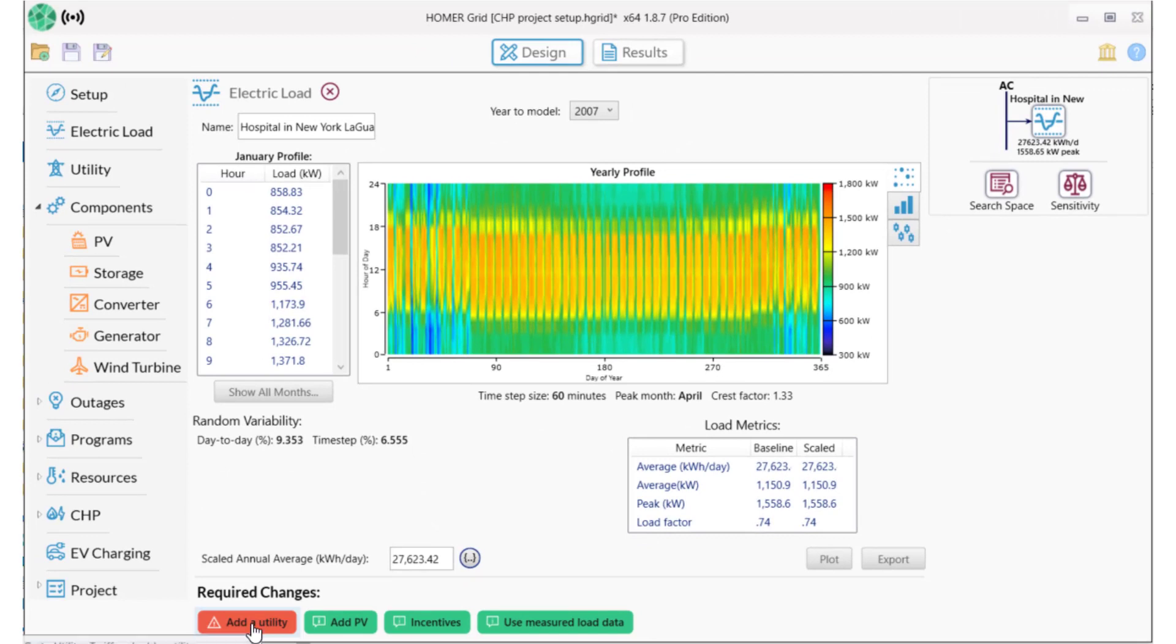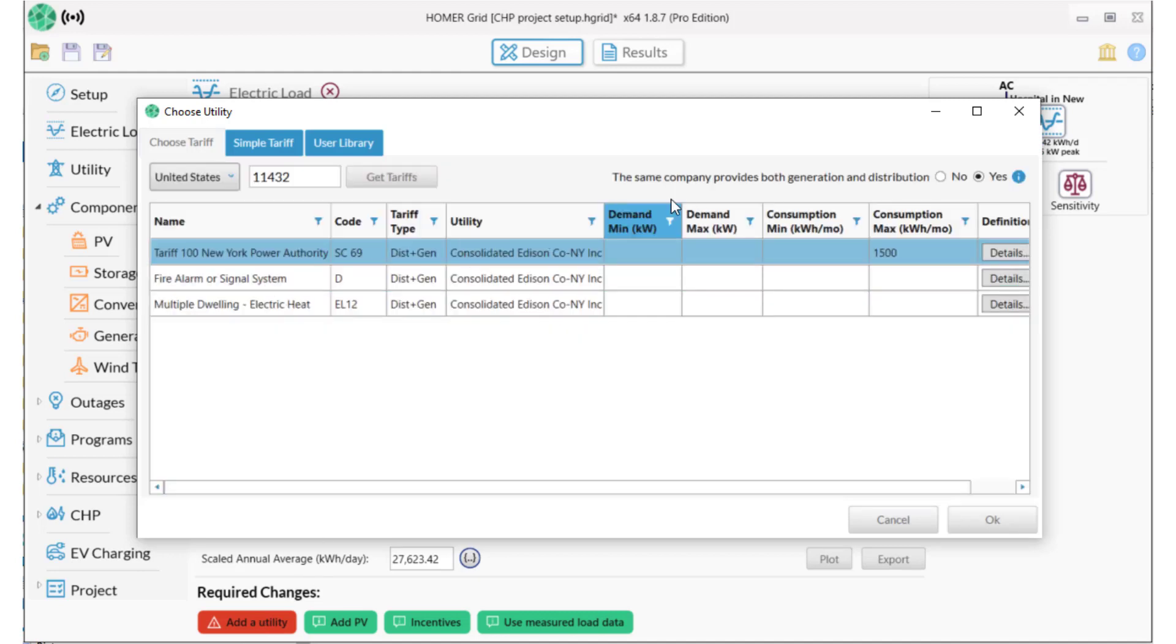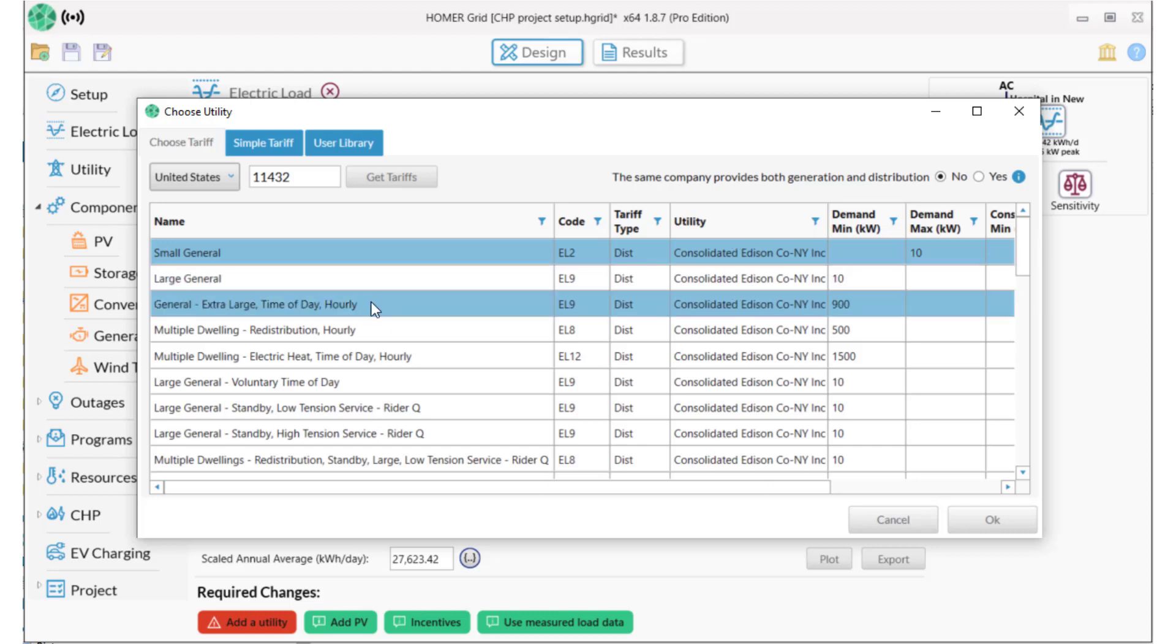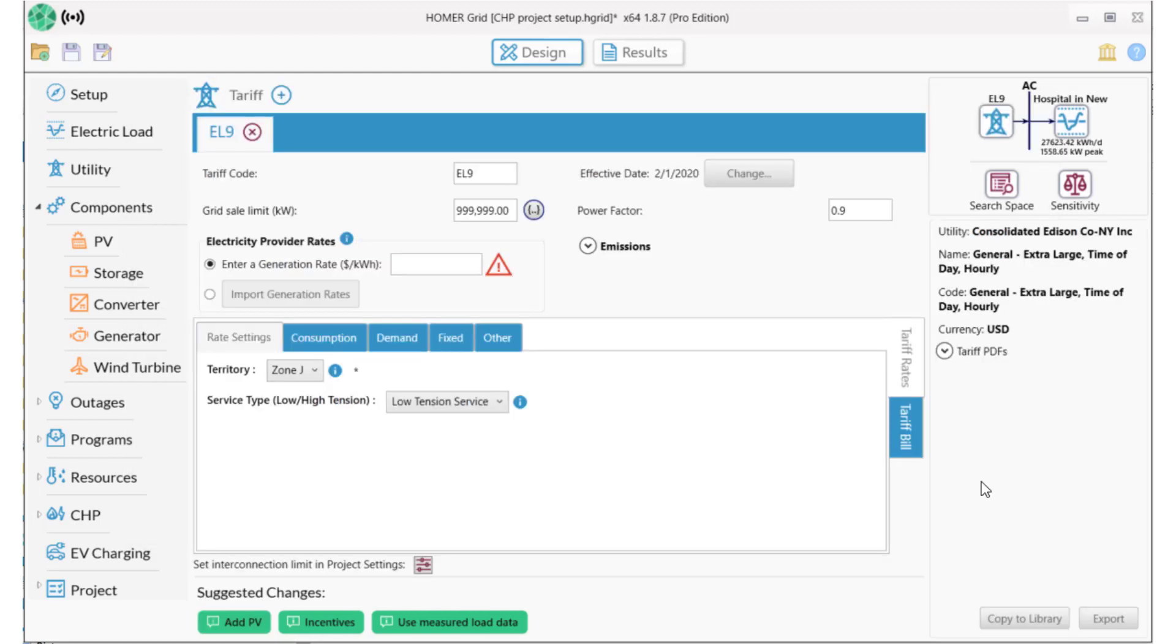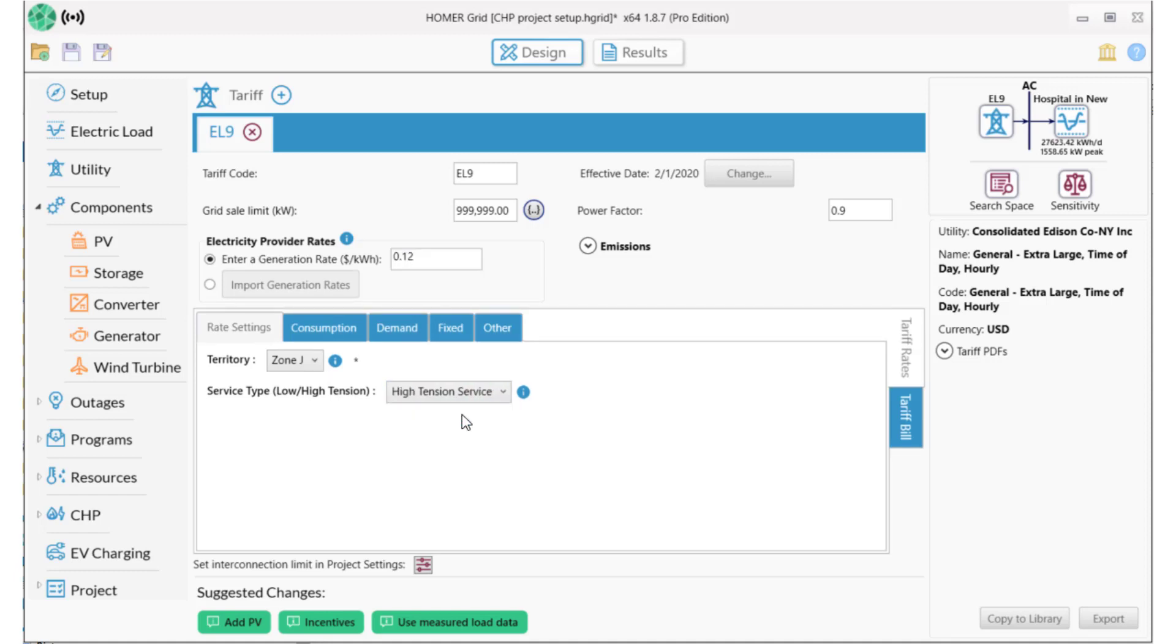Now I'll add a tariff using the GenAbility database. This region is served by Con Edison, which is a deregulated utility that charges for transmission and distribution, and then another company charges for supply. So I select No to this choice regarding generation and distribution, find the tariff that I need, which is the general extra-large time of day hourly. Then I need to add a generation rate, and 12 cents per kilowatt hour is the average for this area, so I'll use that and then I'll select the high-tension service.